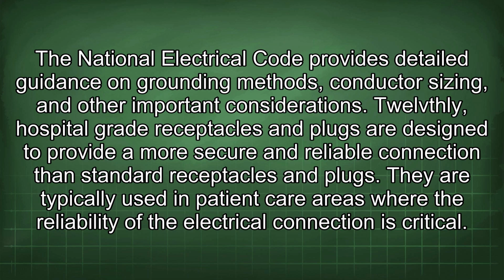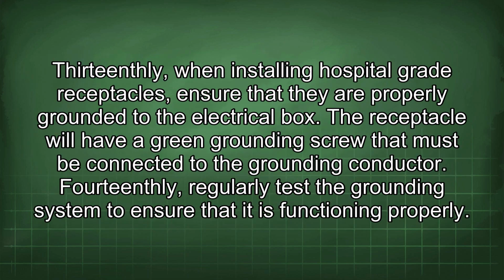Twelfthly, hospital-grade receptacles and plugs are designed to provide a more secure and reliable connection than standard receptacles and plugs. They are typically used in patient care areas where the reliability of the electrical connection is critical. Thirteenthly, when installing hospital-grade receptacles, ensure that they are properly grounded to the electrical box. The receptacle will have a green grounding screw that must be connected to the grounding conductor.